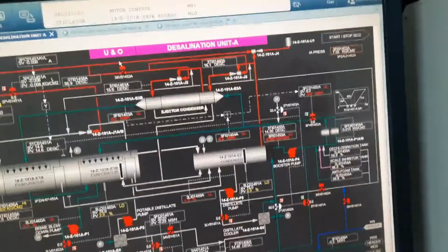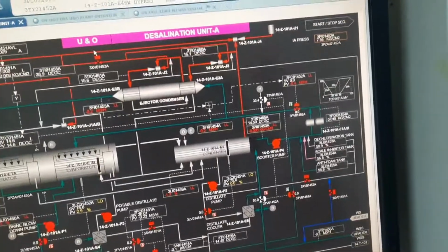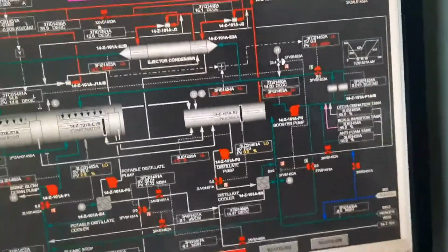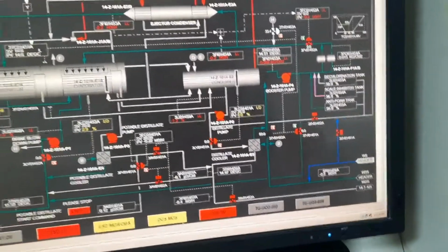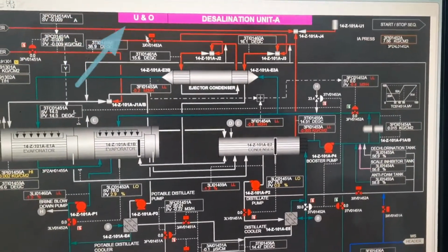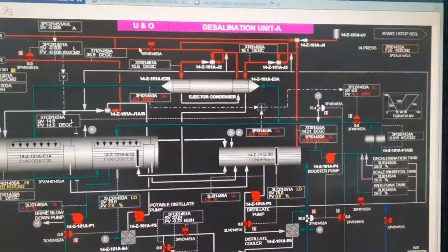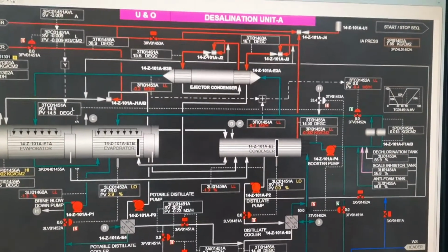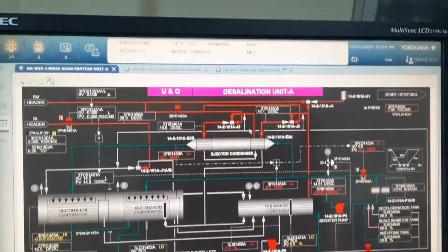So now the circulation is already going on, and the vacuum is also completed. At the same time, now we need to increase the temperature. For the temperature increase, from the DCS side you need to open this SM control valve, and after that open the isolation valve before the SM control valve. When you open this SM control valve and isolation valve, this SM will go to the ejectors J2, J3. So J2, J3 will be lined up and control the temperature.